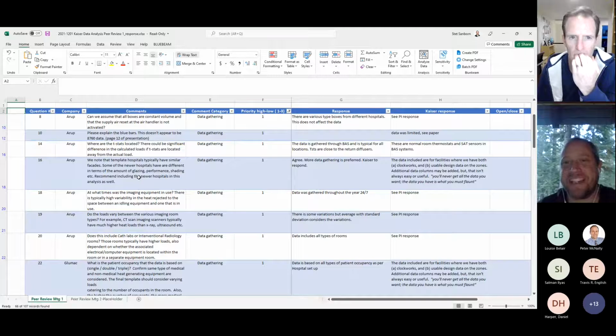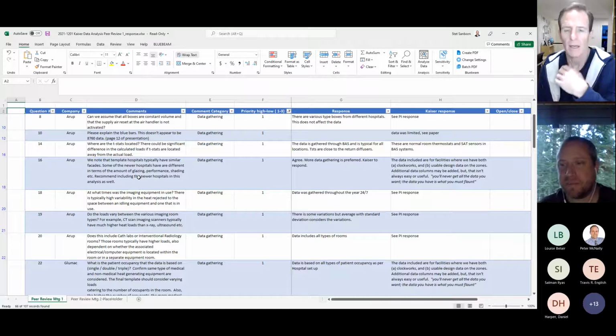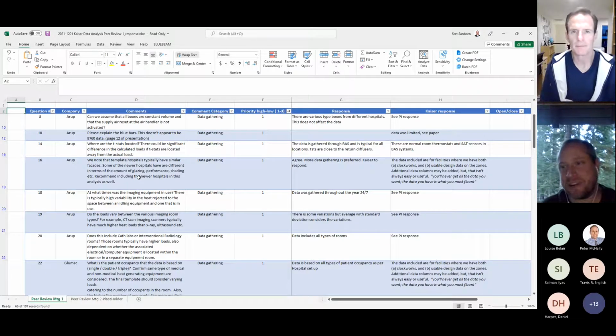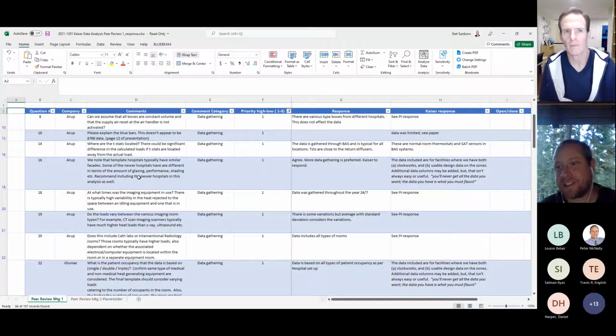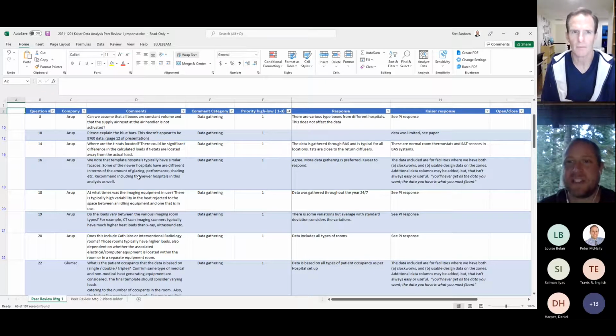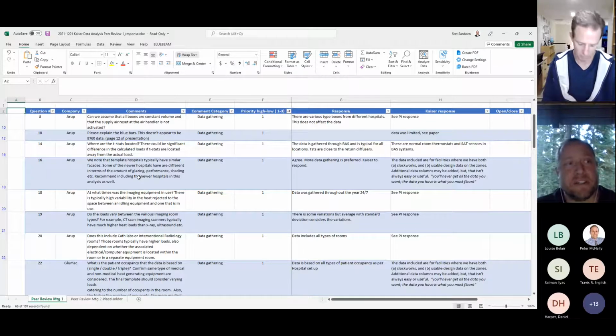We totally agree, and we don't have a data set yet pulled from one of the really recent projects to look at what that aggregate difference is, because it's a bunch of things happening at once. Your walls are getting better, the glass is getting better, but then you have more glass, so it's a confounding impact to just say the envelope is better. We think it generally is, and that the delta to the room loads caused by solar conditions or exterior air temperature is likely reduced, but we don't have data to support that yet, or to know to what degree.